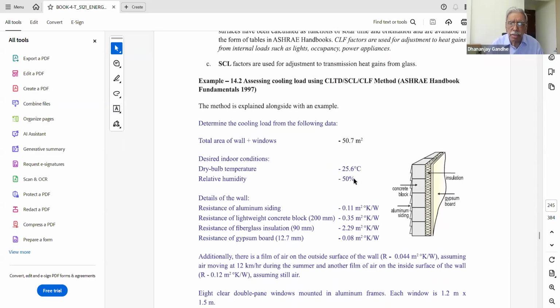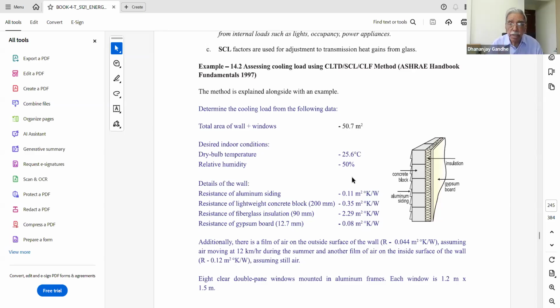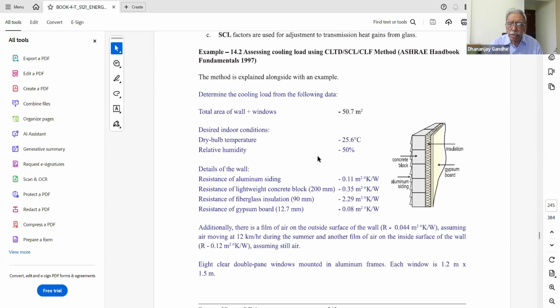So there is an example which is given here. There is a calculation given here. It wants to assess the cooling load in an envelope using the CLTD, SCL, and CLF method, which is the ASHRAE method. So we'll just go through the calculation so we can understand this method to an extent. It says: determine the cooling load given the following parameters. One is the area of the wall, which is given as 50.7 meters square.